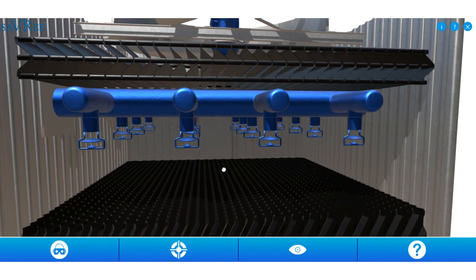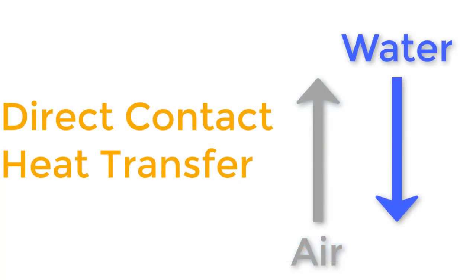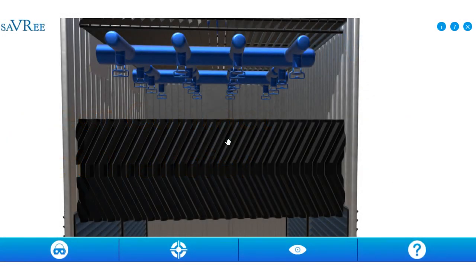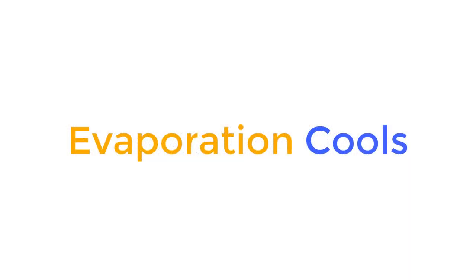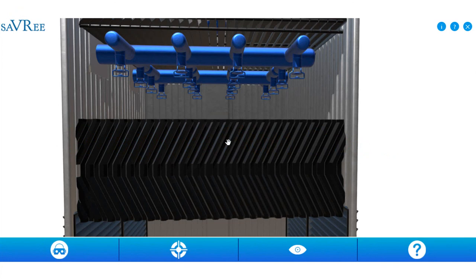The cooling tower actually has two ways of cooling. First, air comes into contact with the water on the heat exchanger and takes the heat away — straightforward heat transfer. What's less obvious is that some of that water also evaporates, creating an additional cooling effect. Think about sweating: your body puts water on your skin, and air blowing across evaporates it, making you feel cooler. It's exactly the same in a cooling tower — the evaporating water provides an additional, if modest, cooling effect.